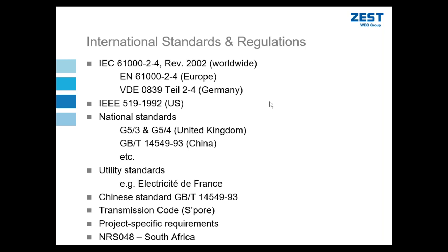Here's a list of some of the standards. There's a lot of standards that talk about harmonics. They vary the requirement for harmonics depending on the type of equipment that is being used, depending on the type of plant, whether it's a hospital, whether it's a utility, or whether it's a mine, can vary the requirement for harmonics or harmonic limitation. And a whole lot of other factors. I'm not going to go into detail, but these are just a couple of the standards. The most common that I use on a day-to-day basis is this one here, the IEEE 519 standard, and this one here, the NRS 048 standard. Those two standards talk to more general plant scenarios like a mine, and are more applicable to our applications.